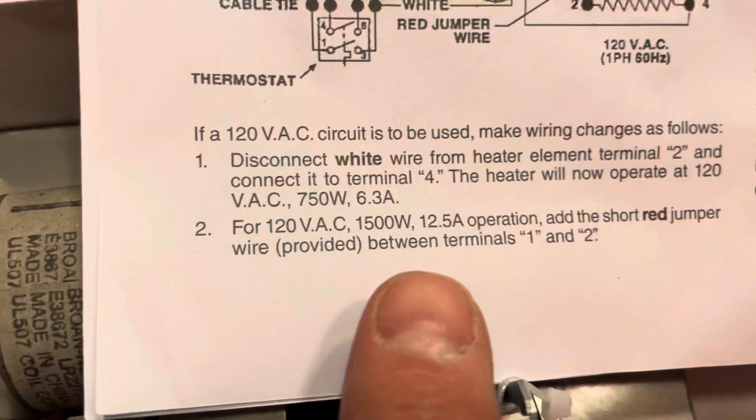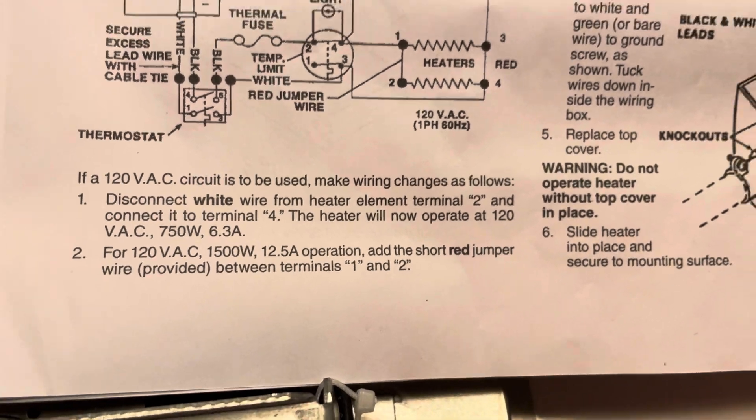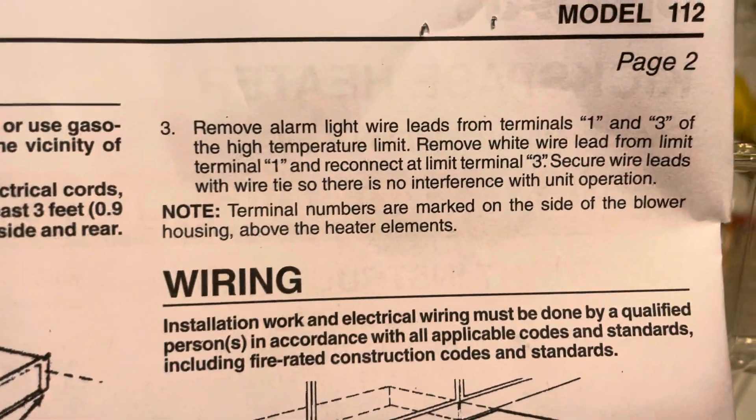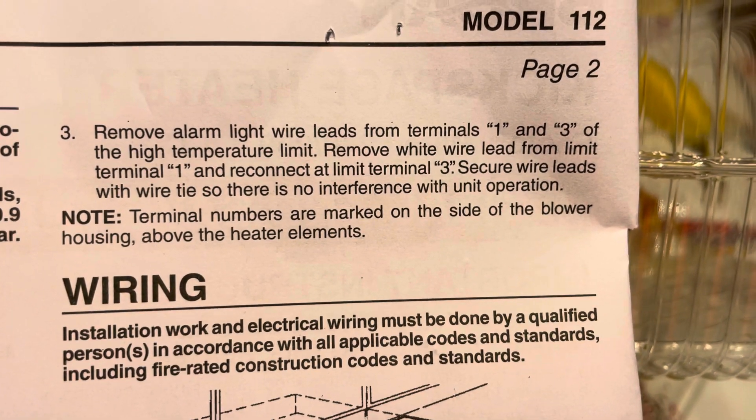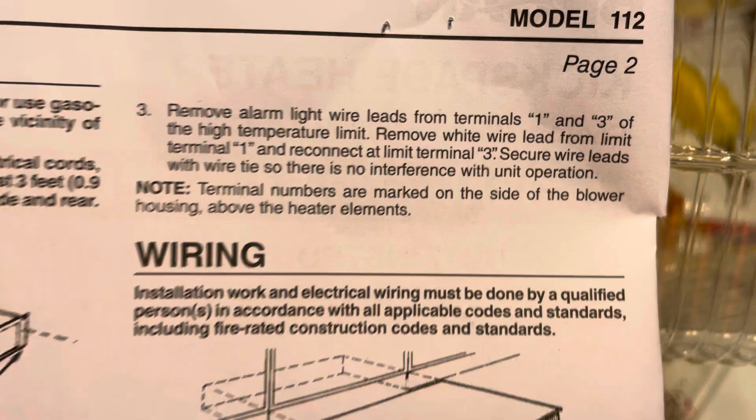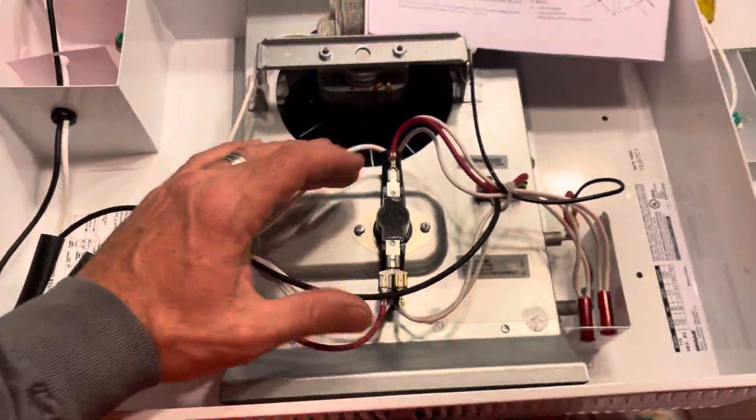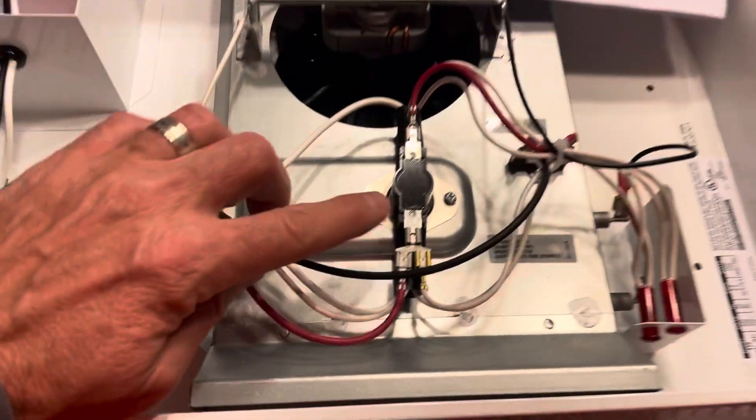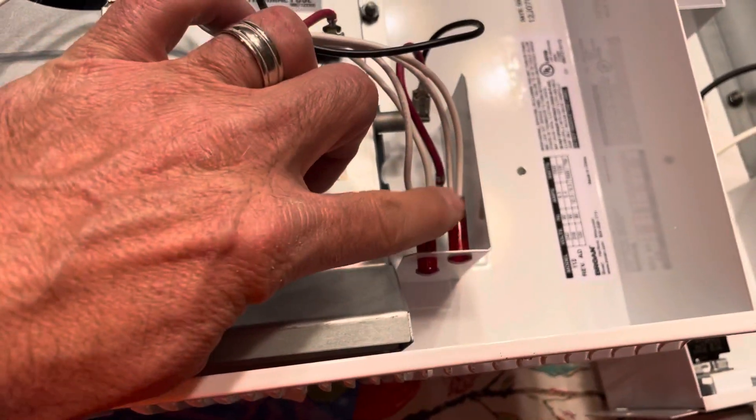And if we did want to operate it at the 1500 watts, then we would connect this jumper wire between terminals one and two as shown there and as described here under number two. Now it gets a little tricky when we go to step number three. Number three is remove the alarm light wire leads from terminals one and three of the high temperature limit.